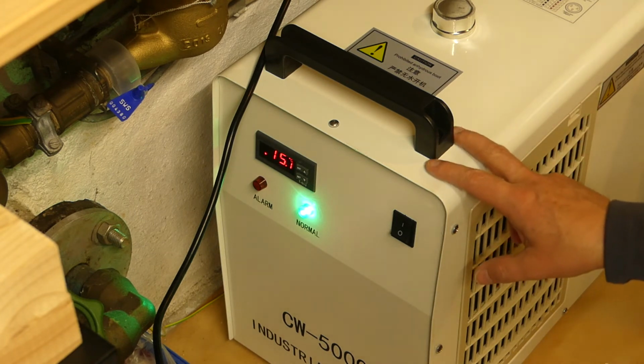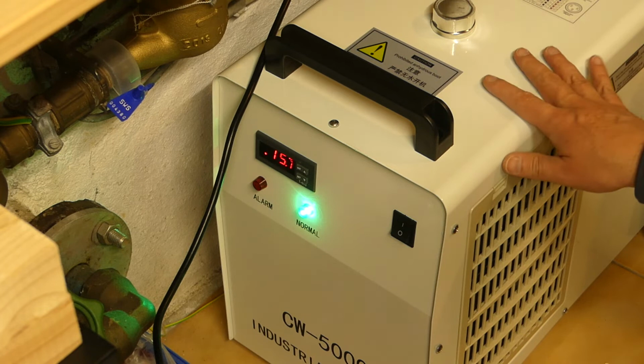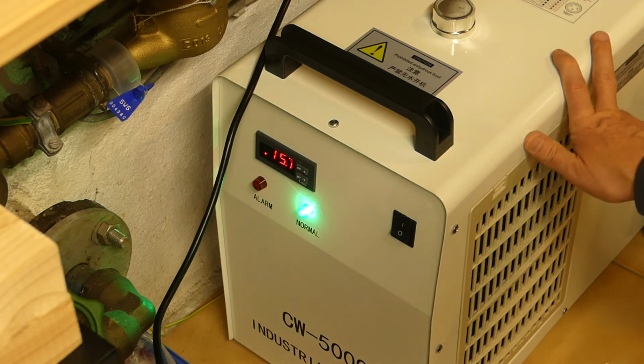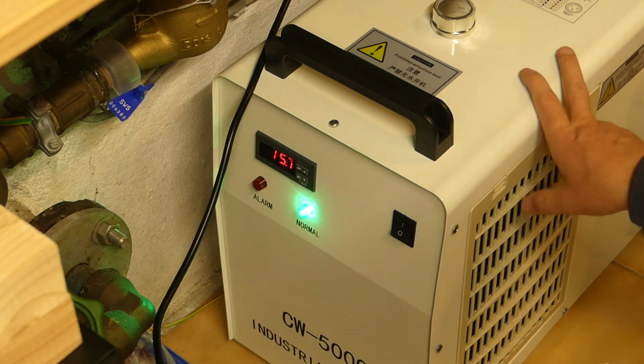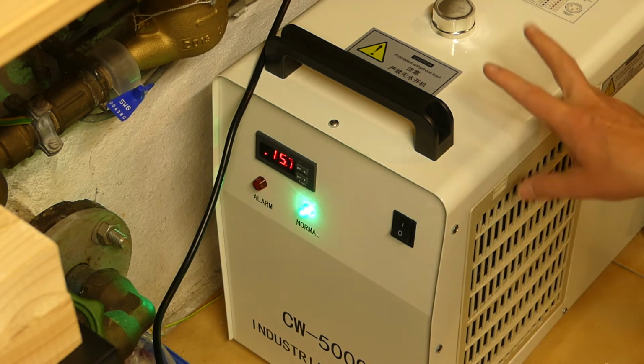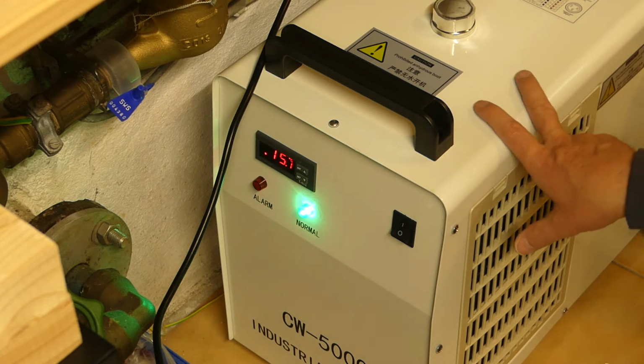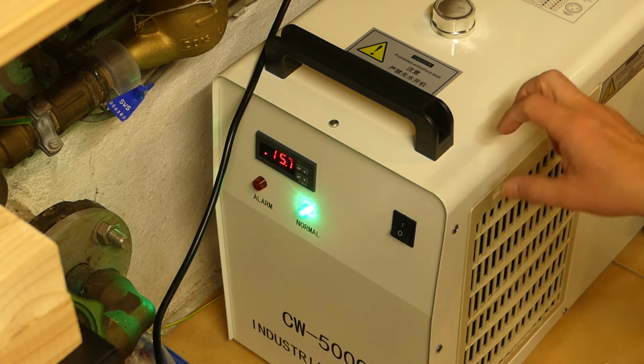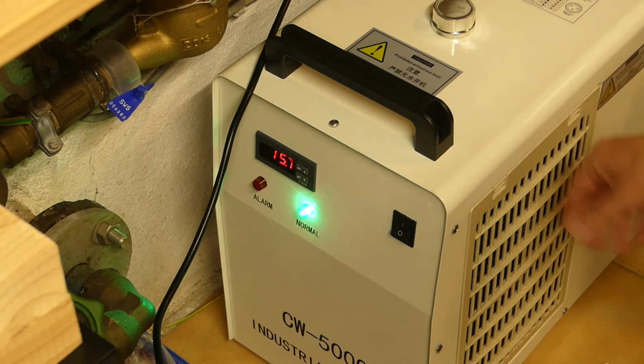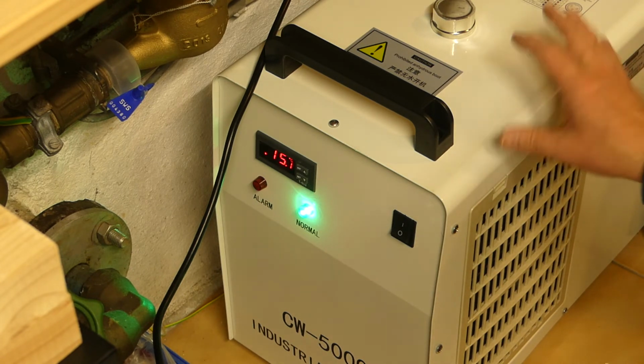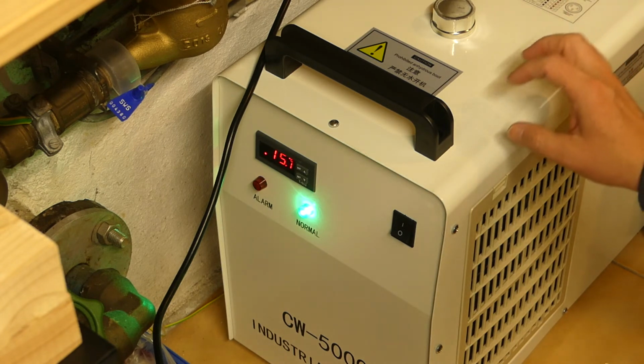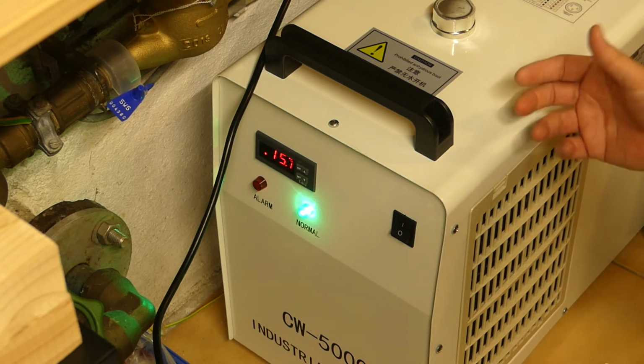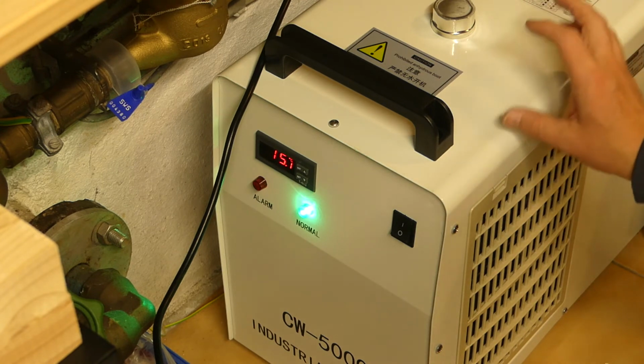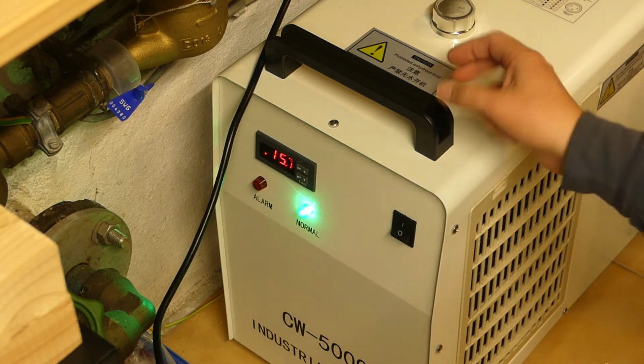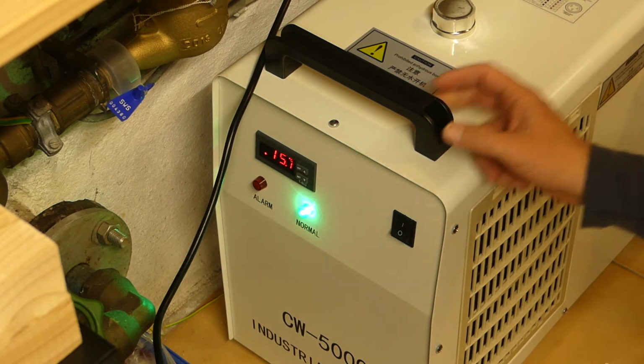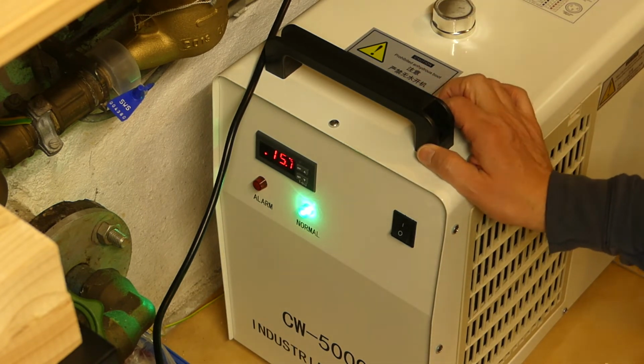It is set to 16 degrees, so the cooler will turn on at 16.8. The active cooling will turn off at about 15 point something, but then it basically spends all the pressure that it has built up in the compressor to keep cooling until all the active compressed refrigerant has been used, and that brings the temperature down to about 14 degrees, which I suppose is lower than I'm willing to go.